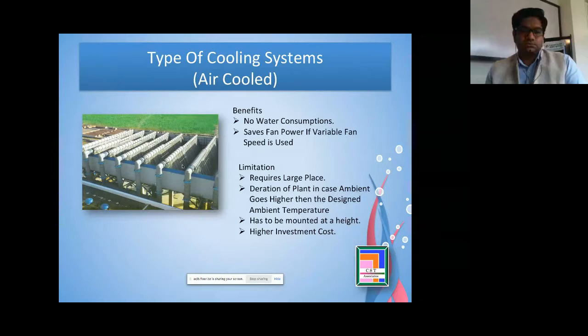So if we have designed these air cooled condensers at, let's say, 40 degrees centigrade or 45 degrees centigrade, and somehow, with global warming, ambient temperatures go higher, like 48 or 49 degrees centigrade, or sometimes with short cycling and extra heat on the power plant, it may go up to 50 degrees centigrade also. At that time, derating of the plant occurs. They have to reduce the steam to compensate for that surface area. Third, it has to be mounted at a height, and there is a higher investment cost.